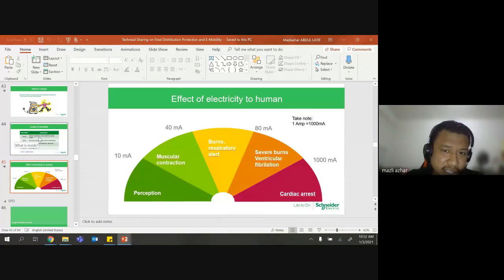A new residential house surely has an RCD as protection, meaning the developer will install a 10 milliamp RCD directly at the panel at the distribution level, and then you just install a water heater and connect it to the 10 milliamp RCD. But old houses normally don't have it. And some of the installations are sad because some of them are tapping from the lighting circuit. That is super dangerous. If you find out, please call a wireman, or if you have a certificate for wireman, please do a proper installation.